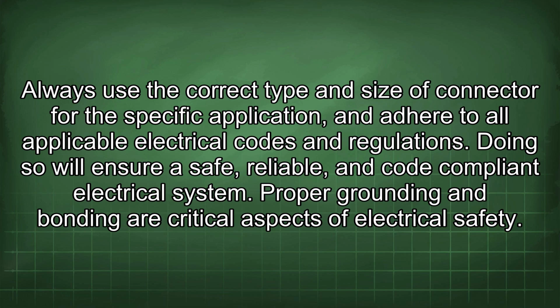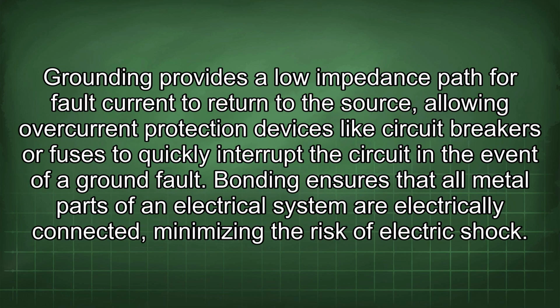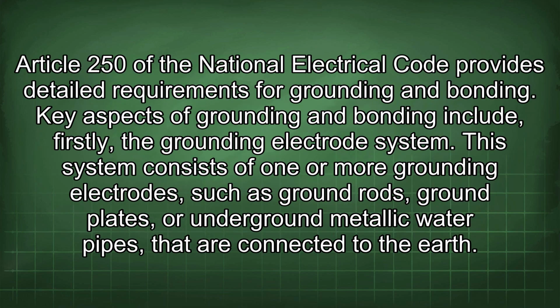Proper grounding and bonding are critical aspects of electrical safety. Grounding provides a low-impedance path for fault current to return to the source, allowing overcurrent protection devices like circuit breakers or fuses to quickly interrupt the circuit in the event of a ground fault. Bonding ensures that all metal parts of an electrical system are electrically connected, minimizing the risk of electric shock. Article 250 of the National Electrical Code provides detailed requirements for grounding and bonding.